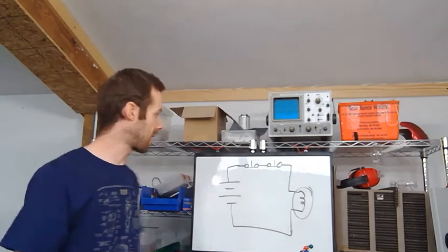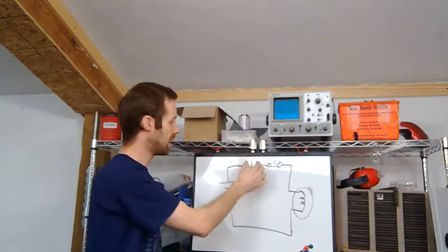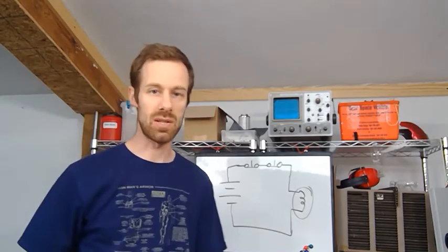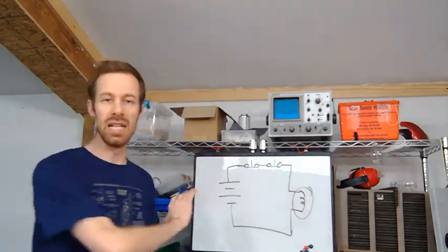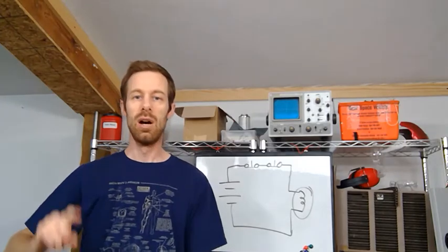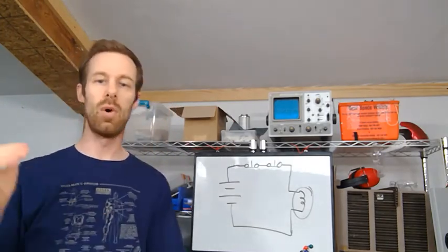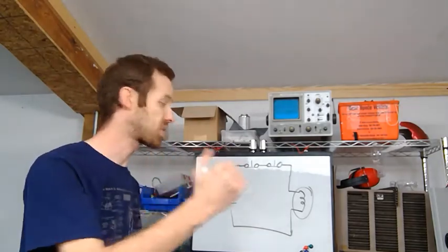No matter which of these buttons I press, if I press down on the button, the contacts will open and electricity will stop. That's an emergency stop. You press the button, electricity stops. E-stop buttons will always be normally closed, and if there's more than one, they will be normally closed in series with each other.